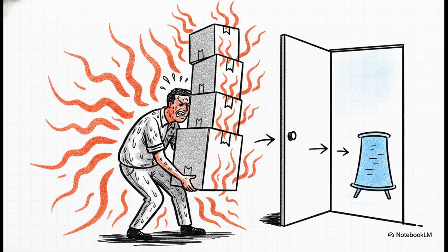If that sounds a little abstract, just think of the sweaty mover effect. Say you want to move some heavy boxes out of your living room. Those boxes represent the heat in your room. You hire a mover, which is your compressor. Now the mover picks up the boxes and carries them out. Great, but lifting heavy boxes is hard work, so the mover starts sweating and radiating their own body heat. By the time they hit the front door, the outside air has to absorb the boxes and the mover's sweat. Your outdoor cooling tower is that front door.